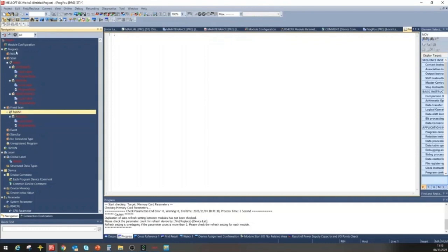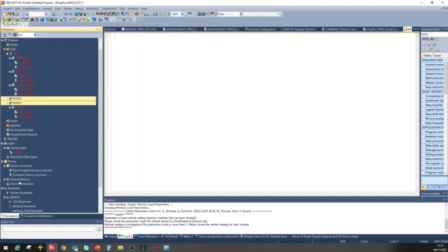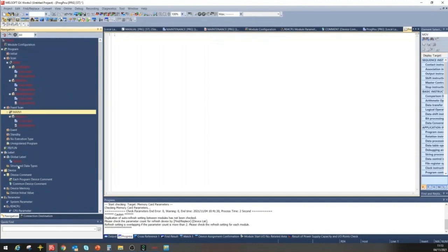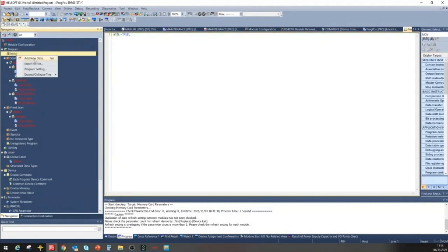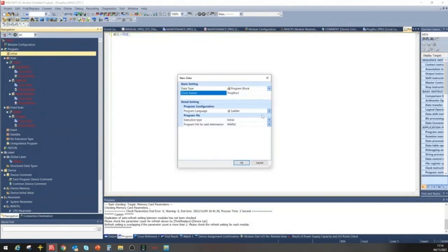Let's go and see the settings. Seeing the settings, I anticipate that the part of enable interrupt is missing. To make this program cycle, in the case we write M10 equal true, here maybe in the initial part I could pass the system function to enable the interrupt. Otherwise, from the moment they are present, our fixed scans would not be executed.